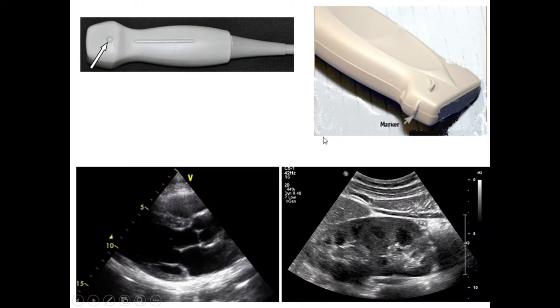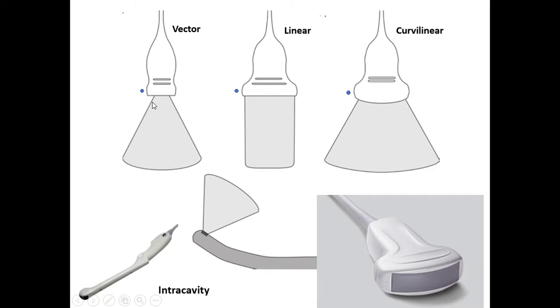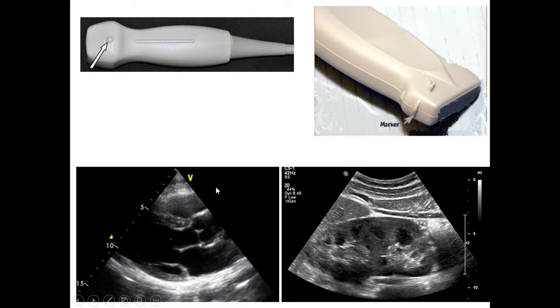At one side of the longest edge of the probe tip, there is a marker — depending on the vendor it can be a ridge, knob, groove, or LED light. Meanwhile, on the monitor image there is also a marker, which can be a letter or symbol. The machine tells us that the marker side of the image will show on a specific side of the monitor. For example, on one image the marker side will show on the right of the monitor, and the other side to the left. On another setting, the marker side will show on the left side of the monitor.